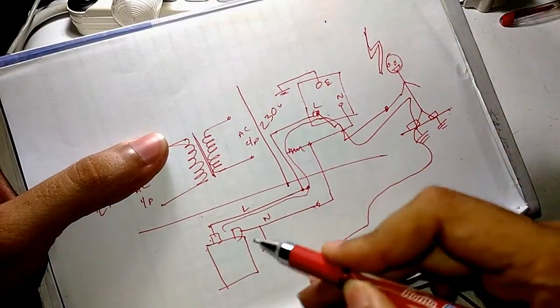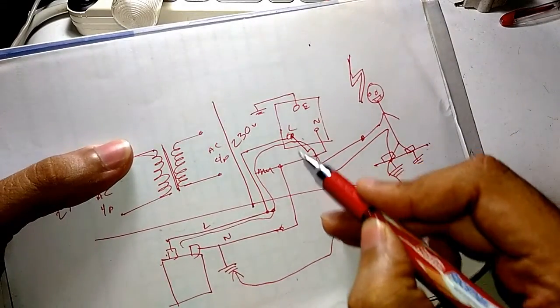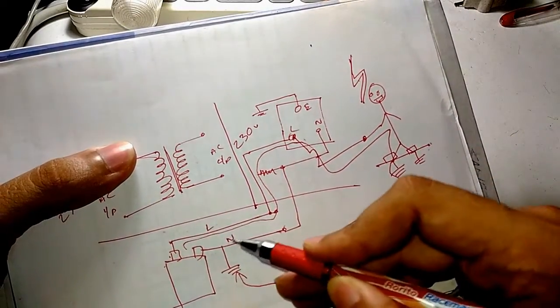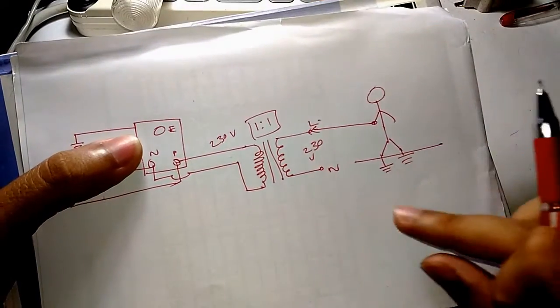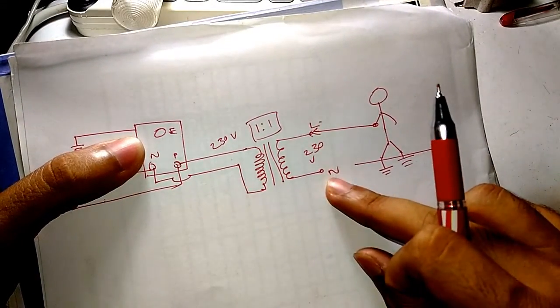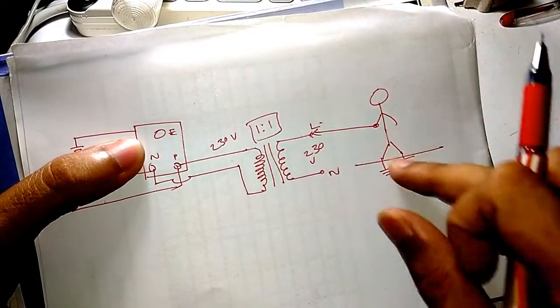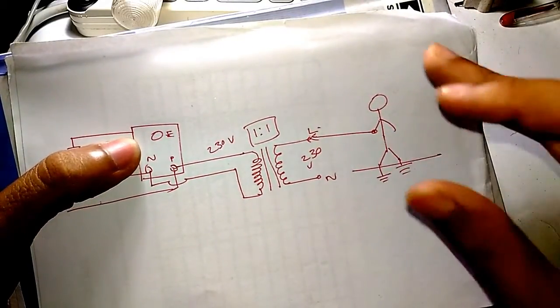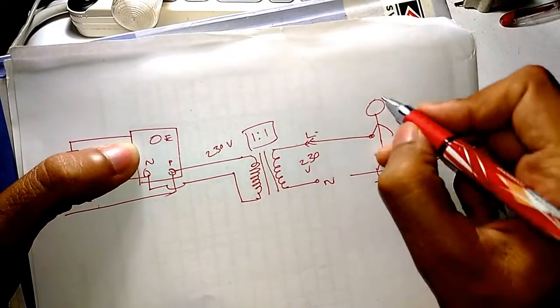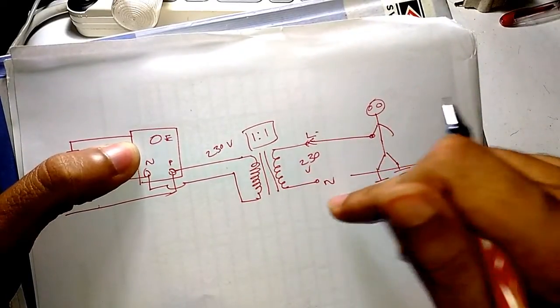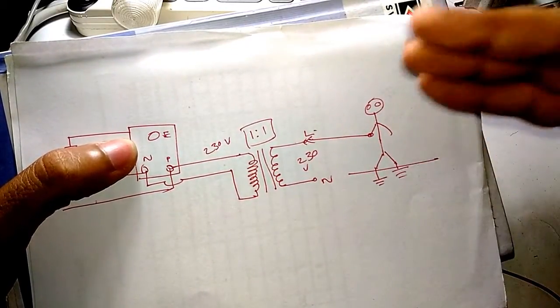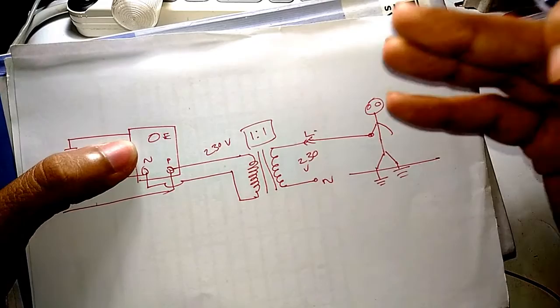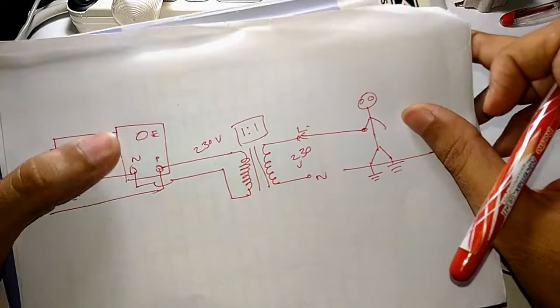If I show this here, since the neutral is grounded, current could flow through his body to the neutral, but in this case, because the neutral is not grounded, he is not going to get a shock. That's how isolation transformers help prevent you from being killed yourself.